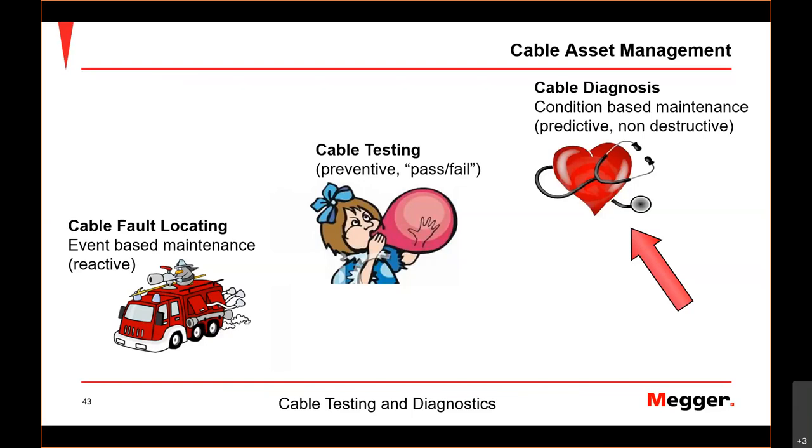If the cable failed, you'll have to do the fault locating, but it would be nice to also do a cable diagnostic measurement, which is non-destructive, which means even if there is a weak spot, the cable will not fail during your diagnostic measurement. The nice thing is you can put it back into operation after your diagnostic measurement. Even if you find that your cable is in bad condition, you can still use it and then judge how you want to proceed. That is one thing we will see today, and we saw in testing also.